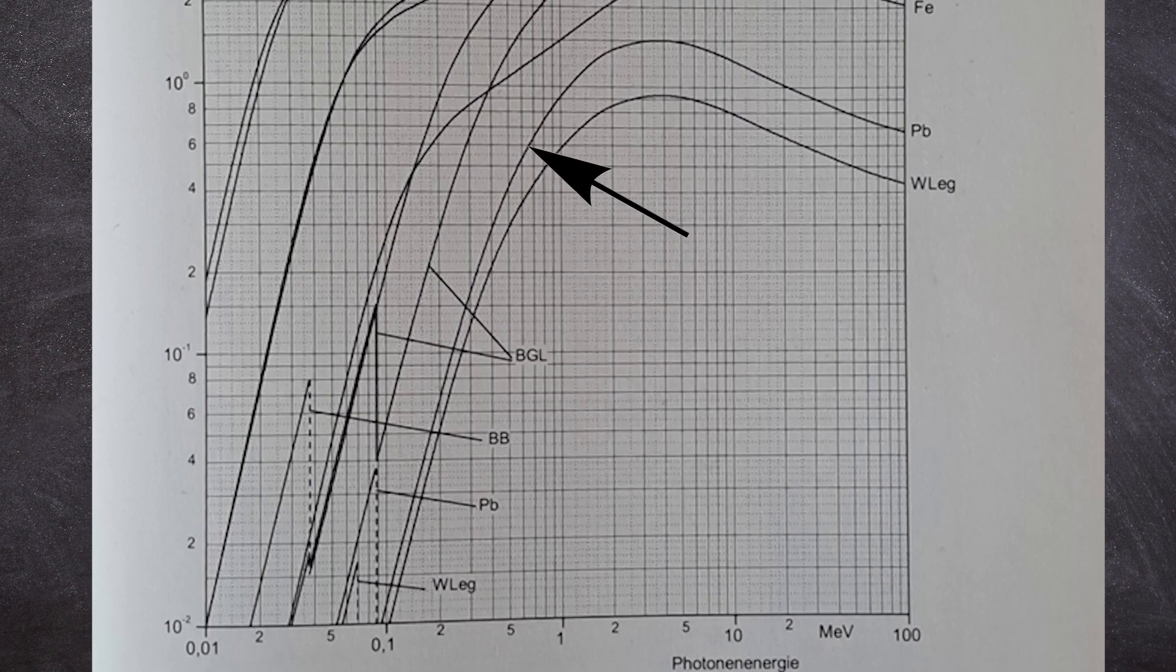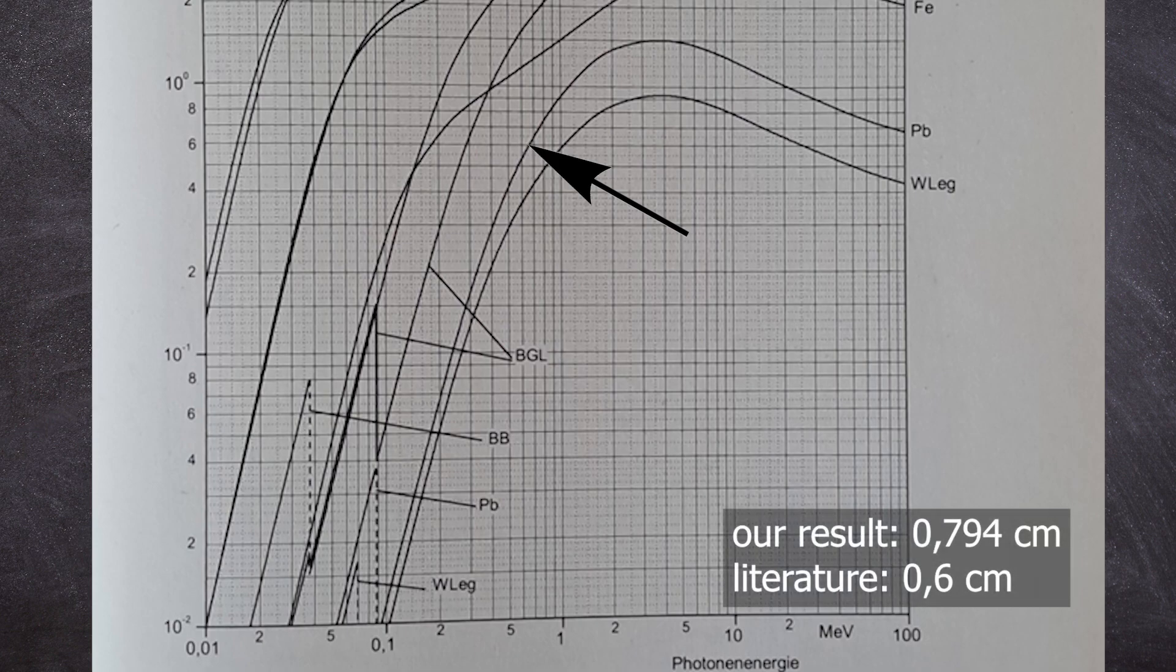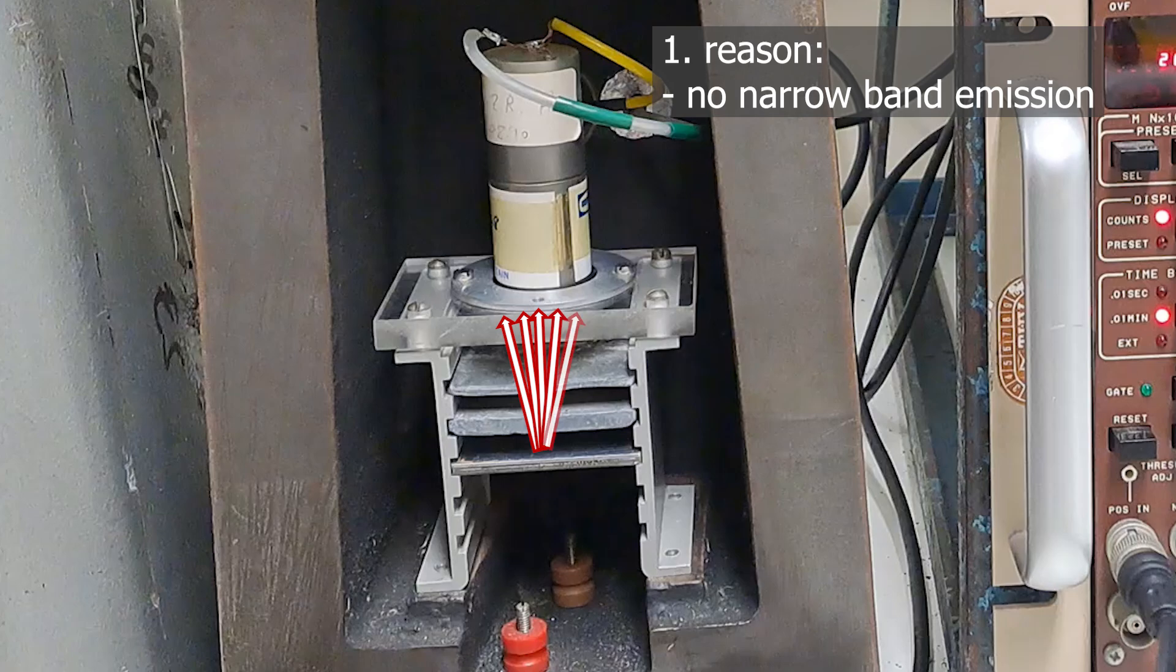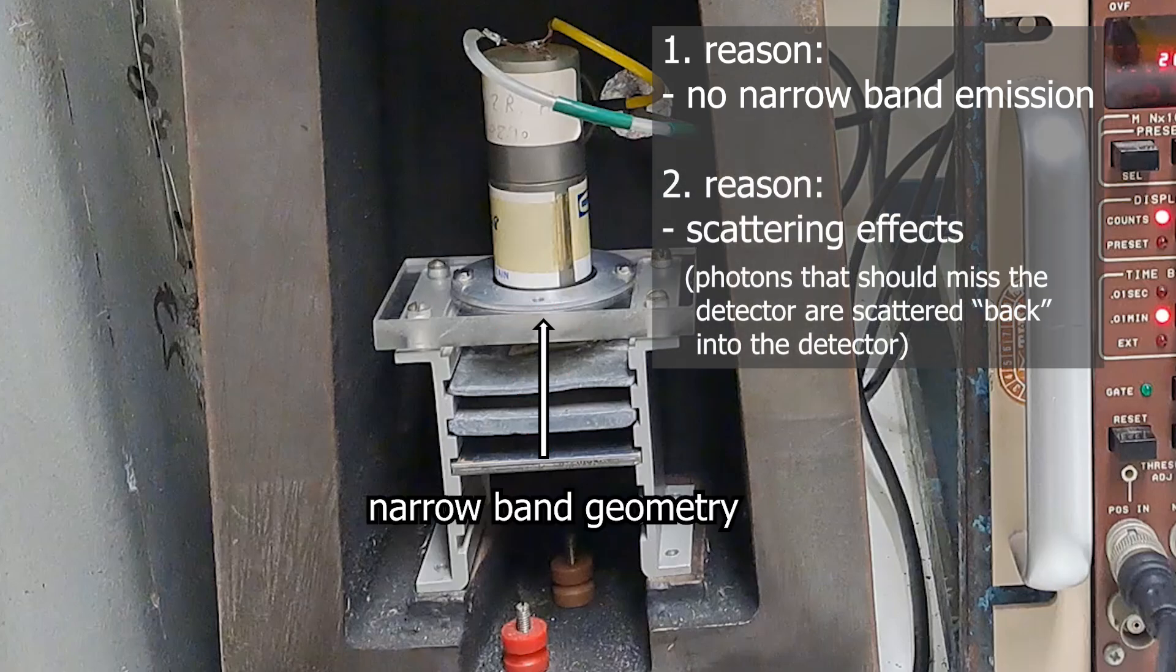Well in the literature the half value layer thickness is for narrow beam geometry. We don't have a narrow beam geometry. We have a point source in the third slot, so the gamma rays hit the lead layer with a broad spread. And scattering effects can occur in practical radiation protection. An additional dose caused by scattered radiation is taken into account with a dose increase factor b.